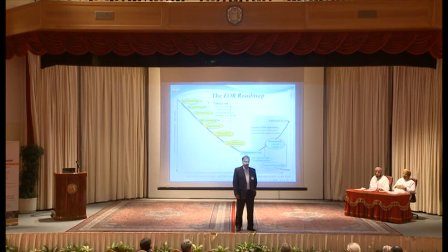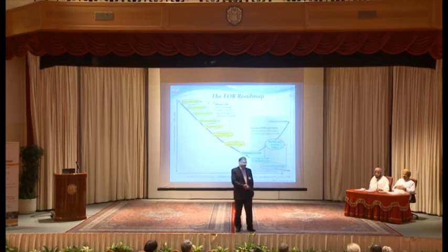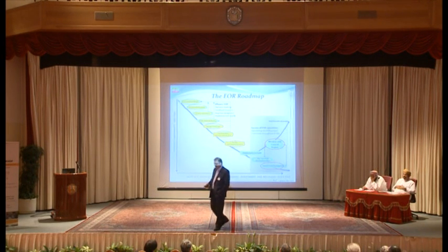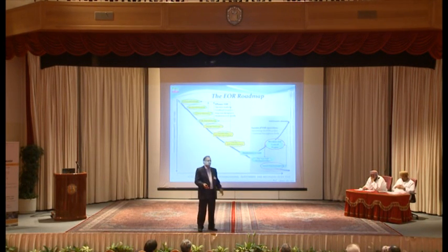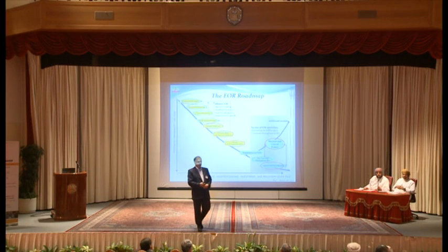This is why your temperature and pressure are less than 200. For example, at a depth of 6 kilometers, we have to apply overburden pressure of maximum 7,000 psi as a compounding pressure, and temperature maybe around 120 degrees centigrade. And it's possible to measure the parameters under these conditions. Okay. Thank you. More questions?